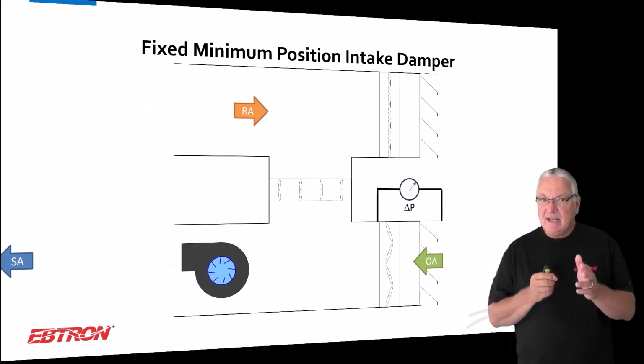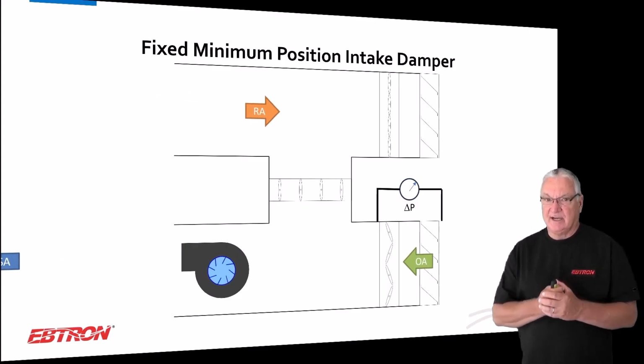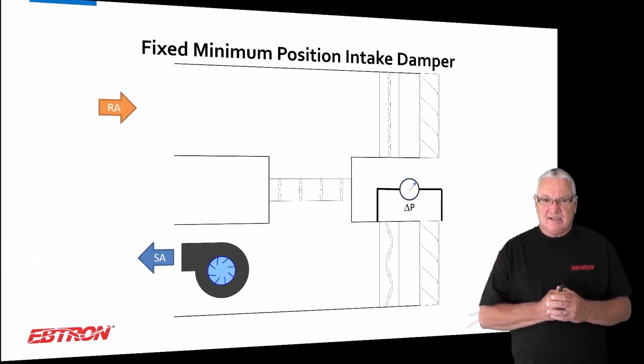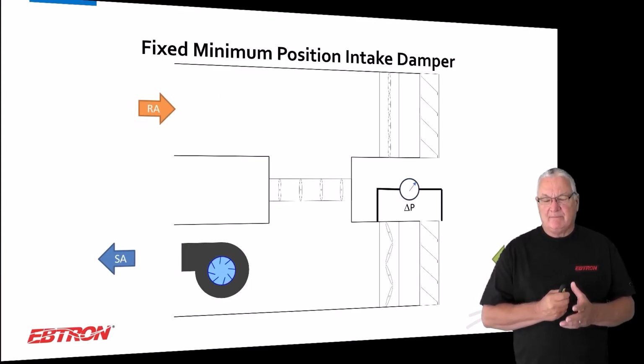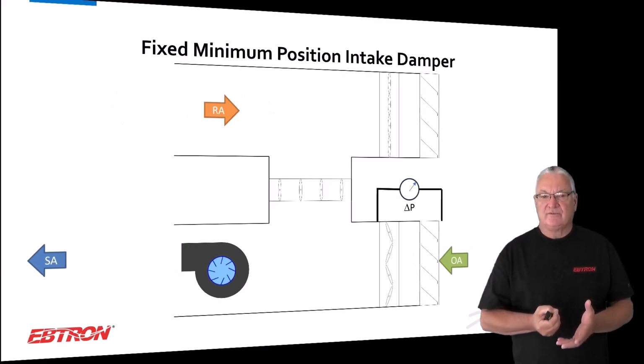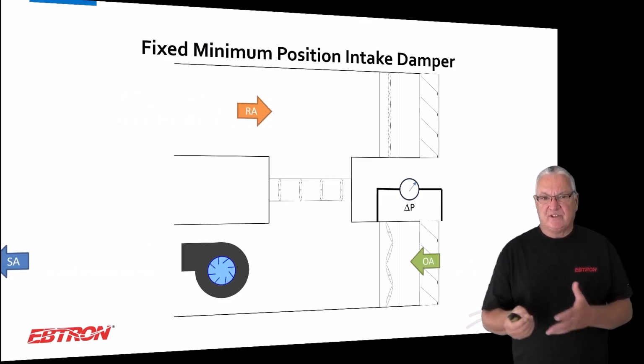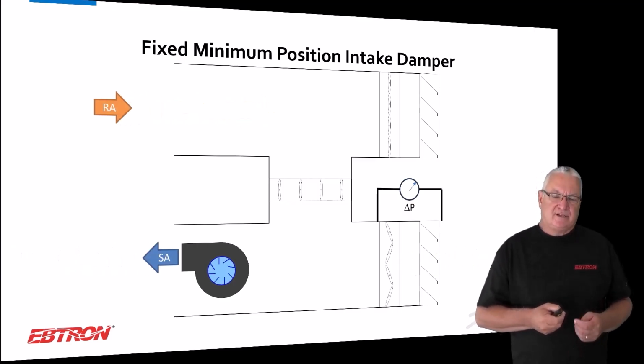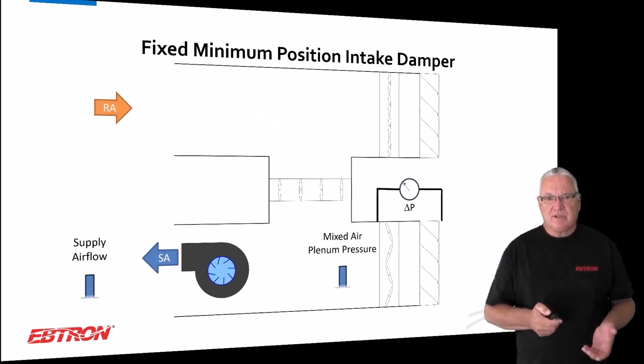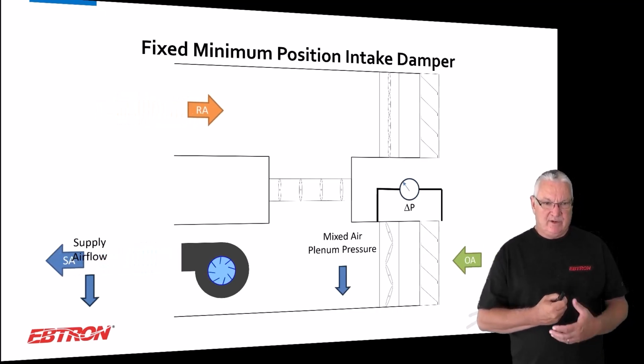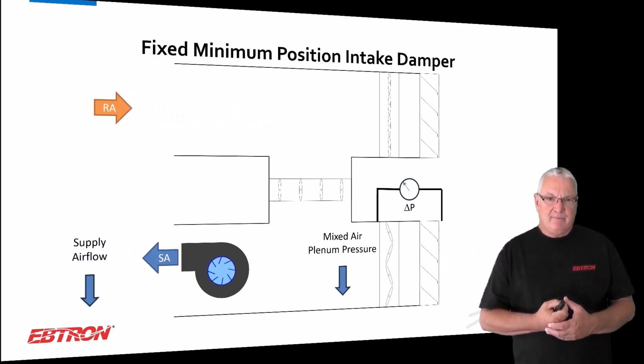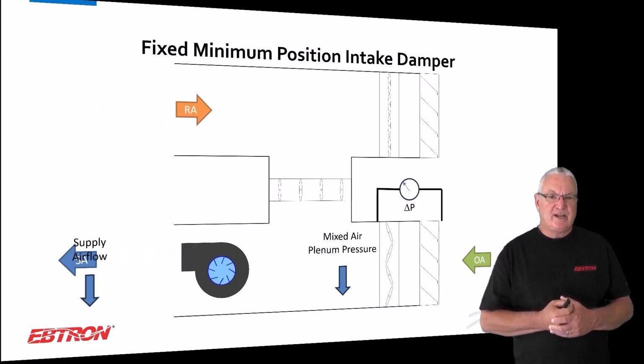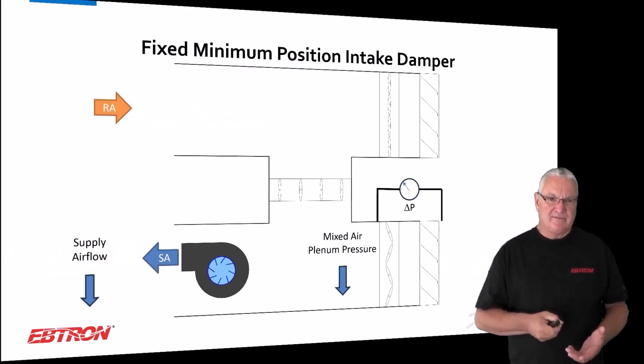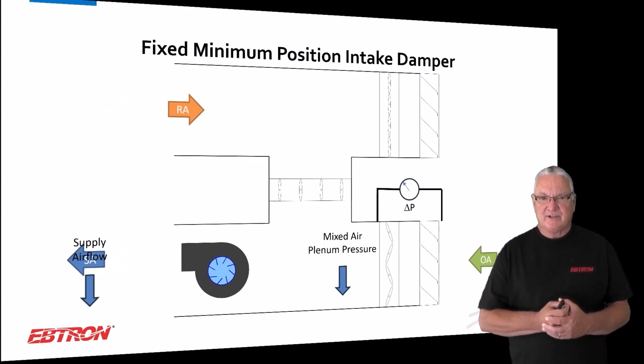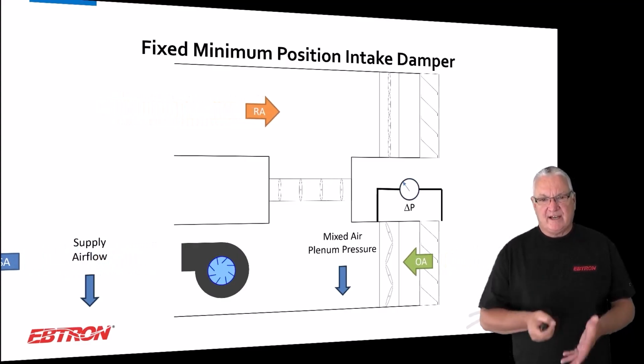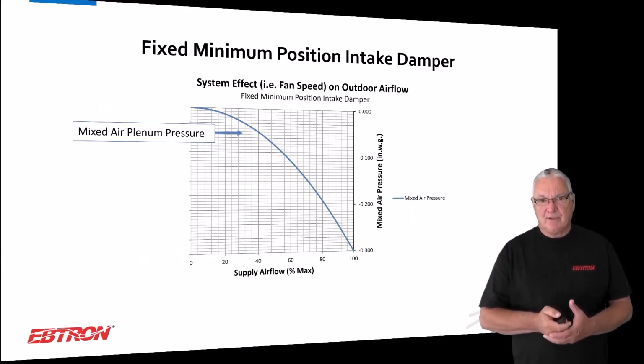It's just, this is an easy way to look at this, okay? So the intake system, if it was just a fixed damper, is a fixed orifice, okay? So it's got a fixed flow coefficient. And so as we change the supply air fan speed, we're going to change the supply air flow, and the mixed air plenum pressure is going to change with it. In this case, if I reduce the supply air flow, I've reduced the mixed air plenum pressure. Over a fixed orifice, the outside air is going to drop, okay?